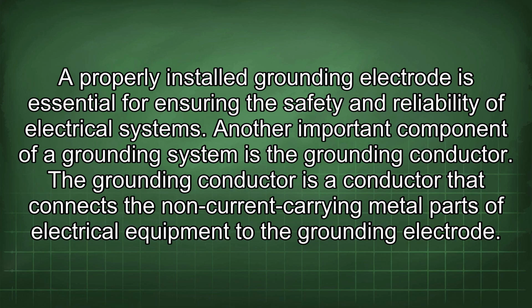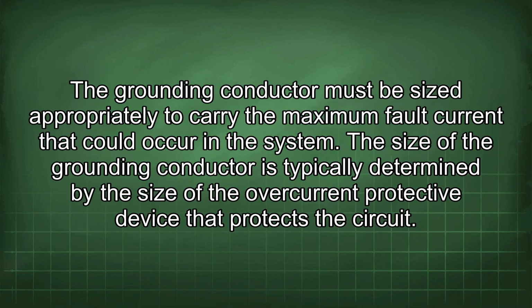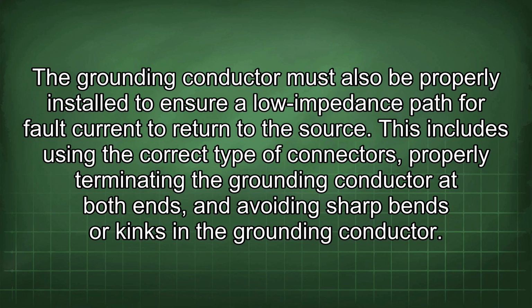Another important component of a grounding system is the grounding conductor. The grounding conductor is a conductor that connects the non-current carrying metal parts of electrical equipment to the grounding electrode. The grounding conductor must be sized appropriately to carry the maximum fault current that could occur in the system. The size of the grounding conductor is typically determined by the size of the overcurrent protective device that protects the circuit.